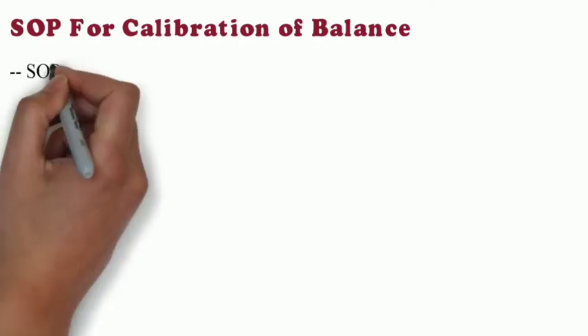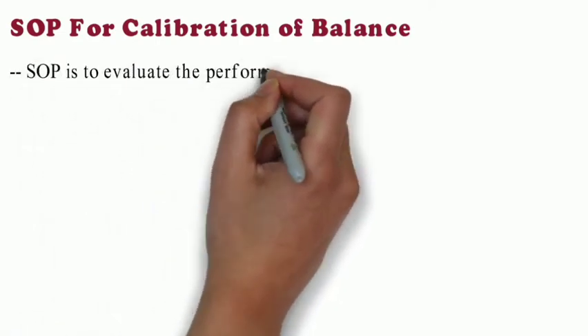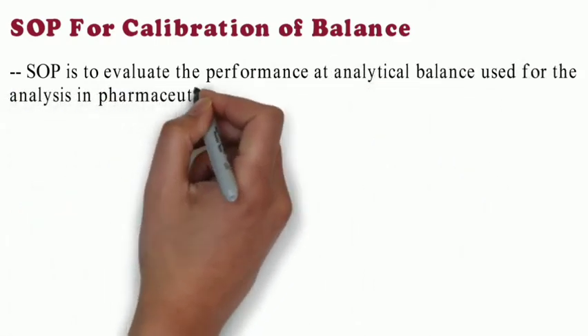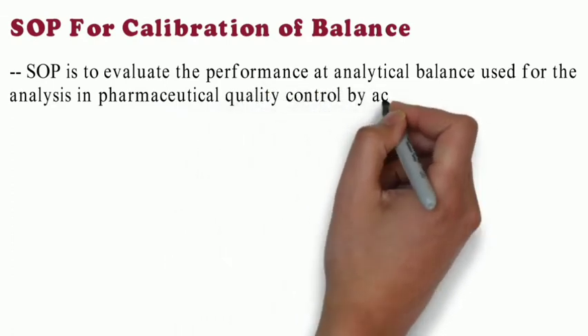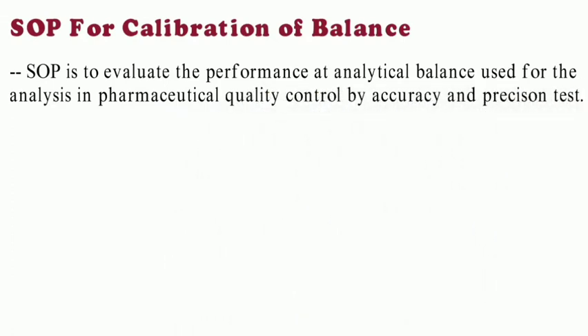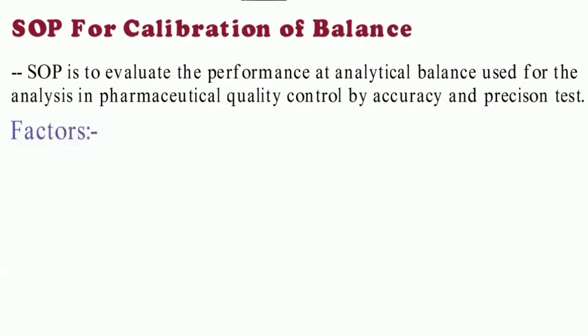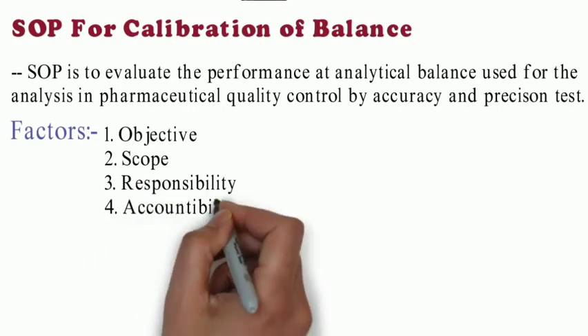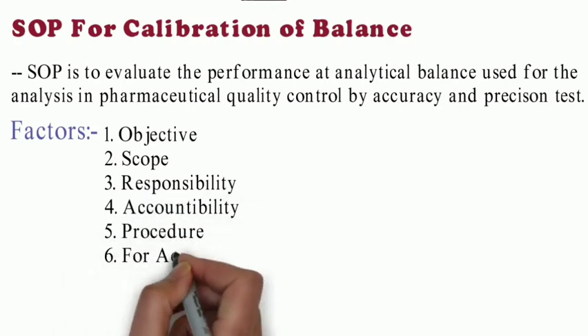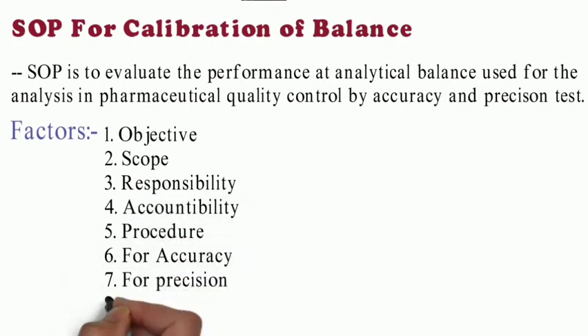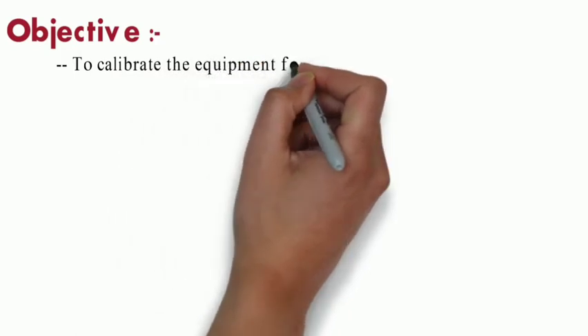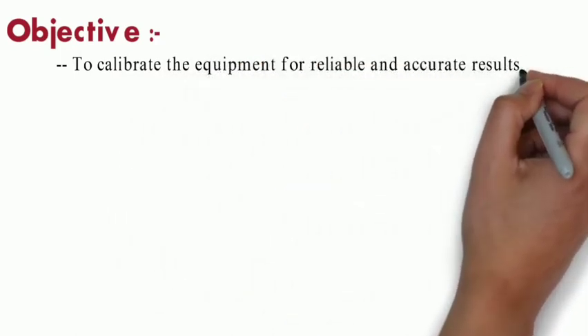SOP to evaluate the performance of analytical balance used for analysis in pharmaceutical quality control by accuracy and precision test. There are factors we will see in SOP like objective, scope, responsibility, accountability, procedure for accuracy, precision, and frequency. In objective, to calibrate the equipment for reliable and accurate results.